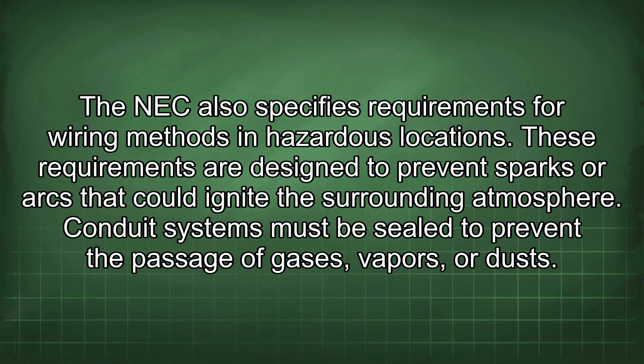The NEC also specifies requirements for wiring methods in hazardous locations. These requirements are designed to prevent sparks or arcs that could ignite the surrounding atmosphere. Conduit systems must be sealed to prevent the passage of gases, vapors, or dusts. Fittings and boxes must be explosion-proof or dust ignition-proof, depending on the class and division of the location. Wiring must be properly grounded and bonded to prevent the accumulation of static electricity.